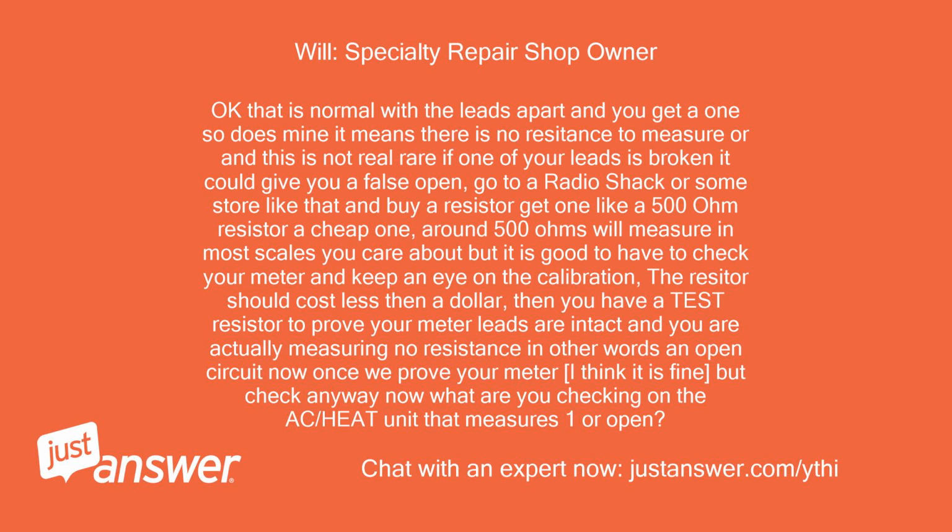Then you have a test resistor to prove your meter leads are intact and you are actually measuring no resistance, in other words an open circuit. Now once we prove your meter, I think it is fine, but check anyway. Now what are you checking on the AC/heat unit that measures 1 or open?